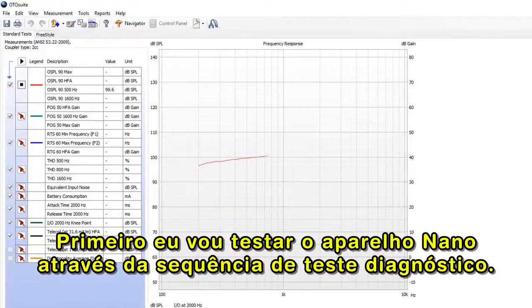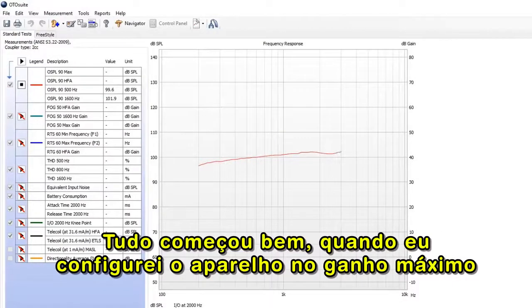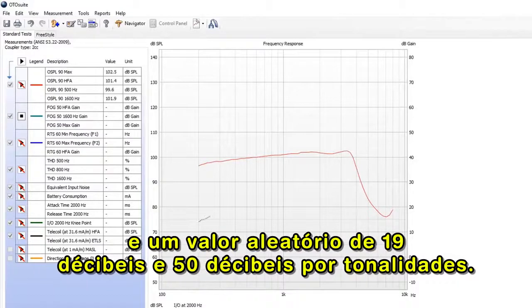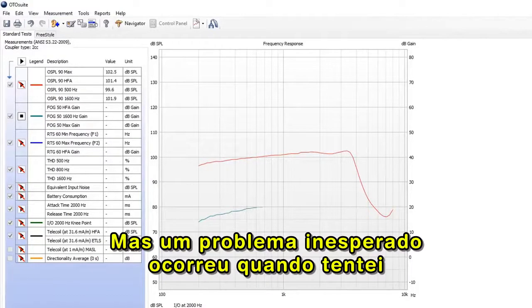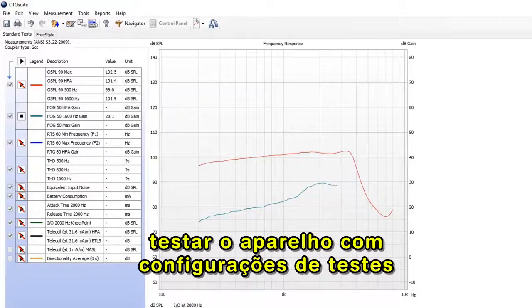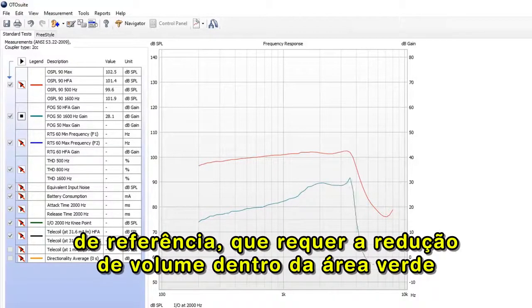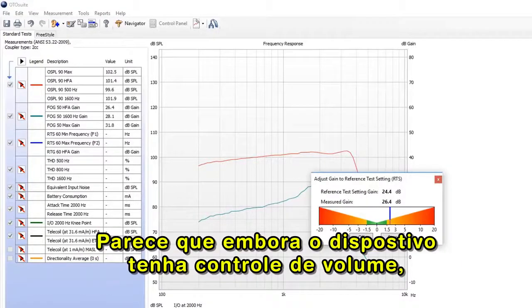First, I will run the NANO hearing aid through the diagnostic testing sequence. Everything started out well as I set the device to full on gain and ran the 90 decibel and 50 decibel pure tones. But then an unexpected issue occurred when trying to test the device at reference test settings, which requires the reduction of volume inside of the green area on this scale.